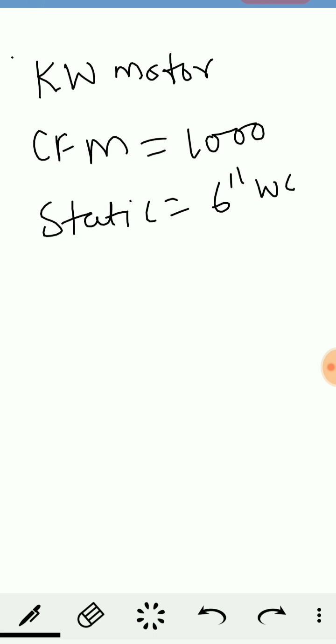For kilowatt rating, for example, we have a CFM for an air handling unit, say 1000 CFM, and its static. Let's assume say 6 inches of water column, and so we want to find out a kilowatt rating for the motor.